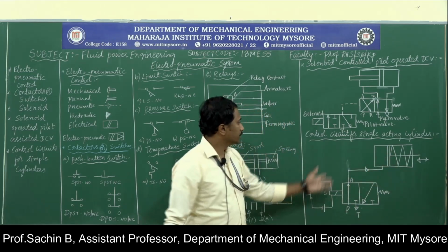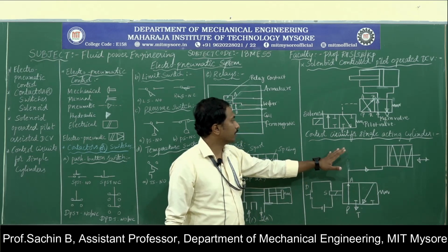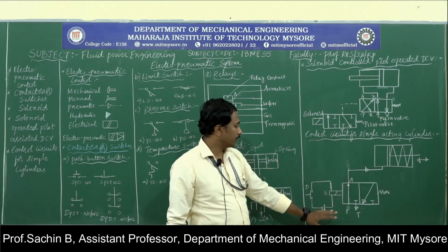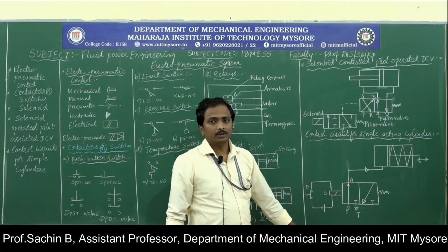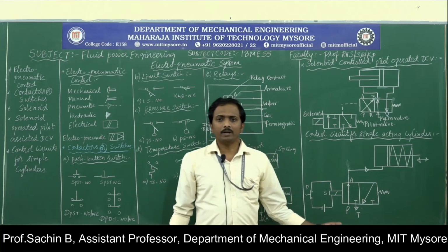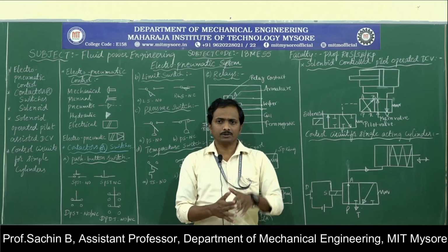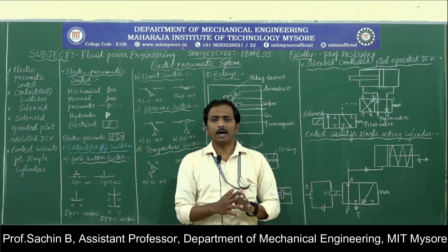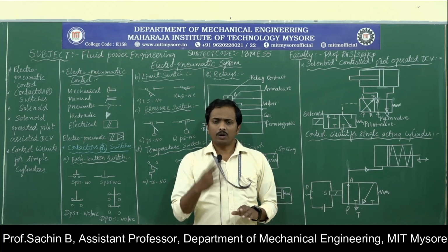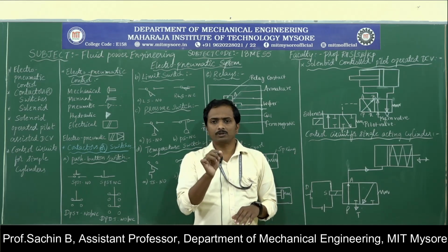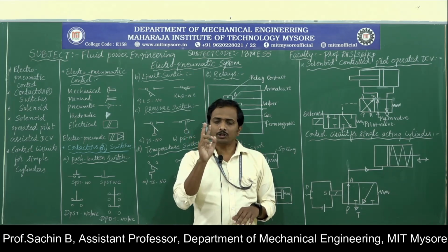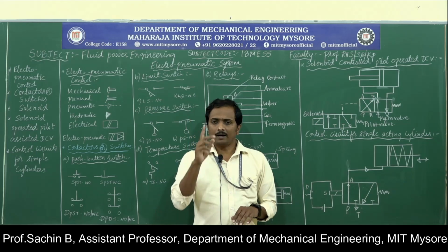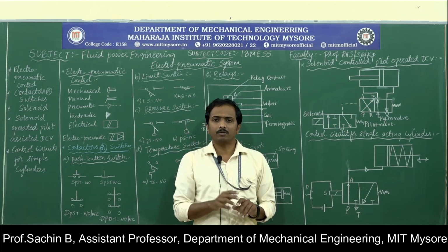That is the simple circuitry that I have drawn for controlling the extension and retraction of the cylinder with the help of a solenoid and a switch contact. If I apply the same thing for double acting cylinders and write the electrical ladder diagram for it, there should be one start button, one stop button, two coils, and one solenoid valve.